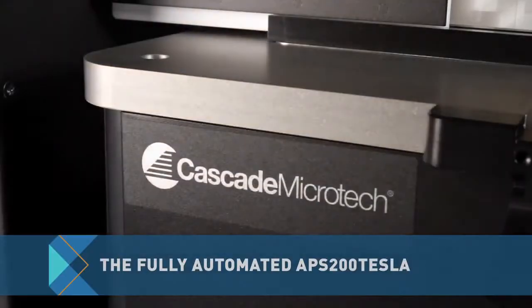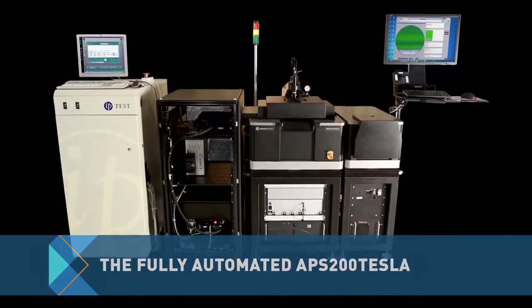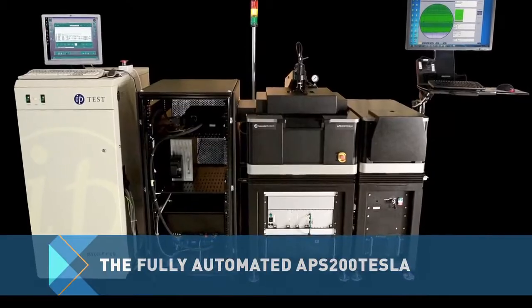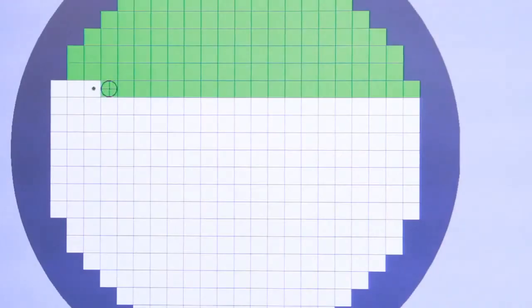Introducing the fully automated APS 200 Tesla wafer prober for production test of high power devices with accurate testing up to 10.5 kilovolts and 400 amps and stepping speeds up to seven die per second.